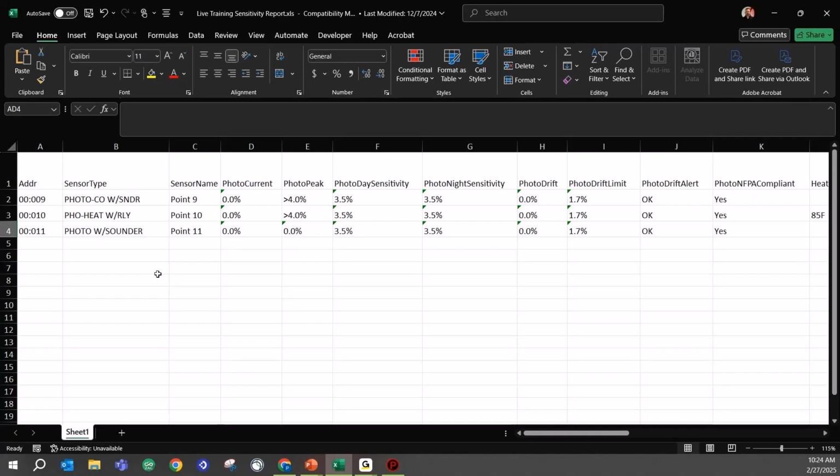The reason why I'm telling you this is we can use that peak value in a very interesting way, in my opinion. So when I would send out test and inspect guys, if we had no service to do before that inspection, I would tell them, pull the SLC, count to 5, and re-land it.